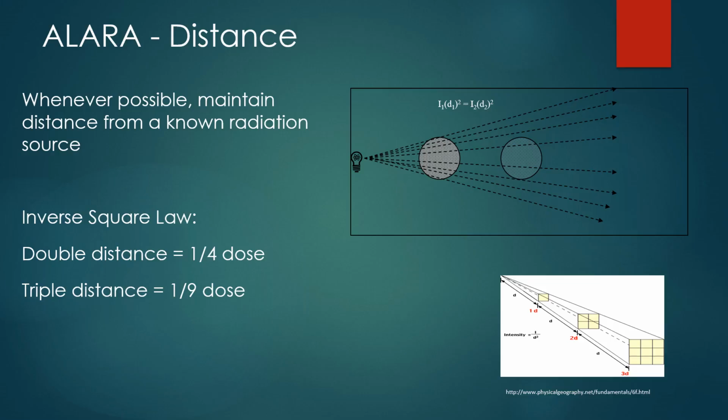Although the technologist taking the X-ray is in a predetermined position, the immediate area should be cleared of personnel to keep their exposure low. In general, technologists performing dental X-rays should try and maintain a distance of 6 feet or stand behind a protective barrier.